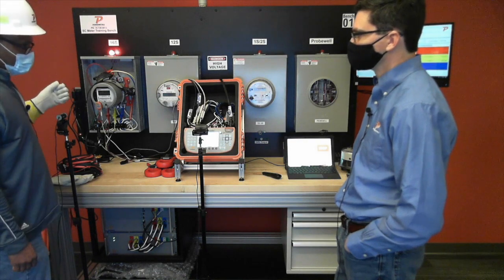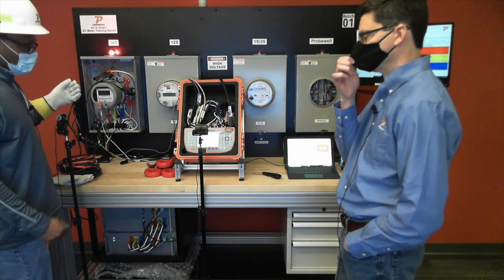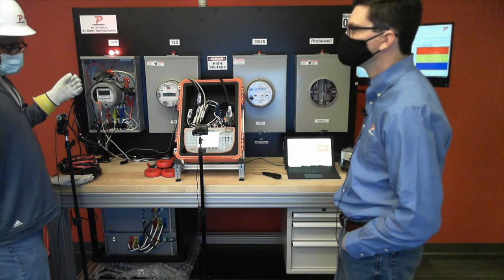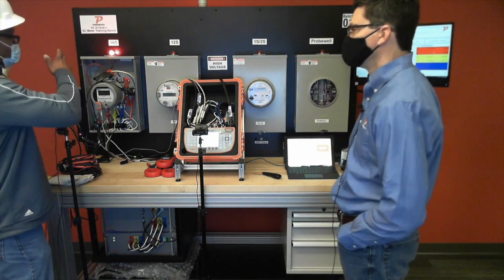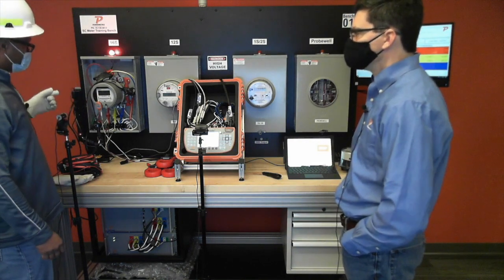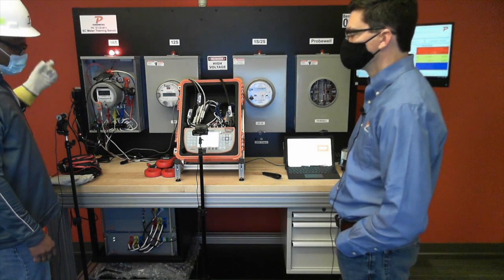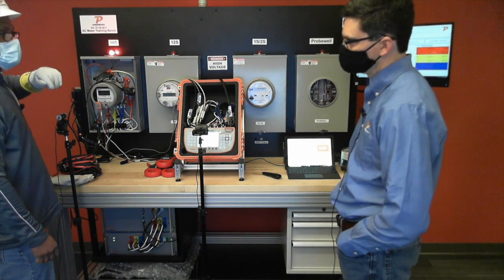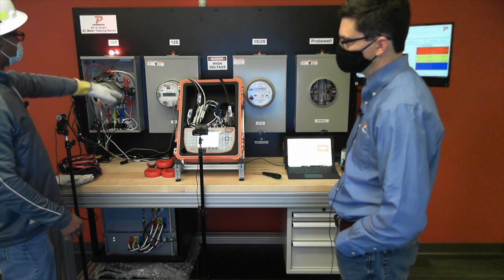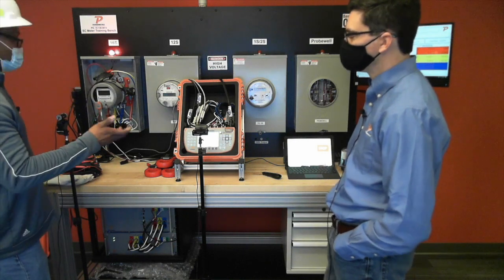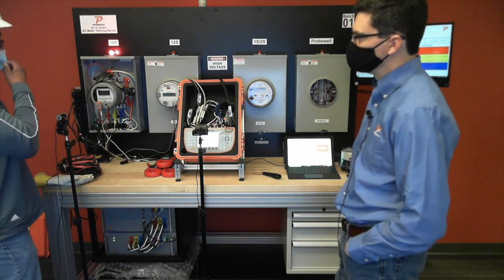But some utility companies, depending on the rated voltage, will require you to pull the jacks. Go talk to the customer, pull the jacks, or there's normally a main right there near the meter can. They want you to talk to the customer first, then pull the handle and pull the meter out. It's just whatever their safety recommendations are, I would follow.